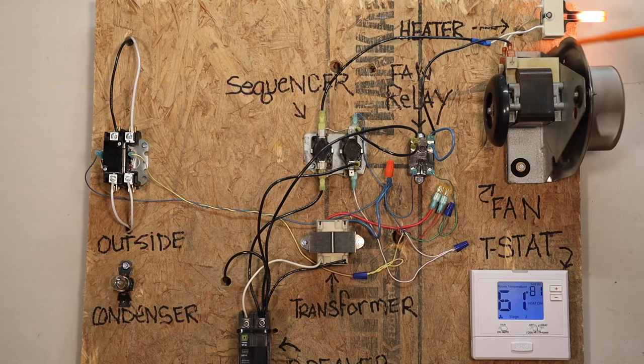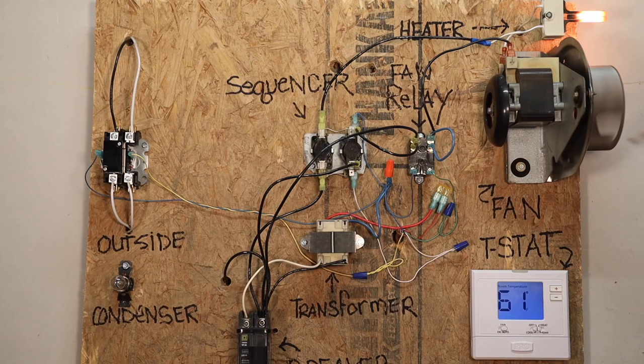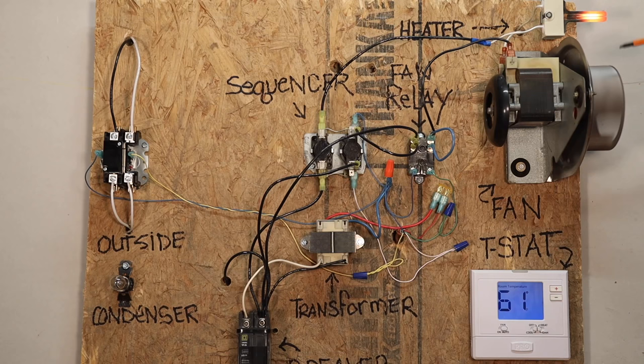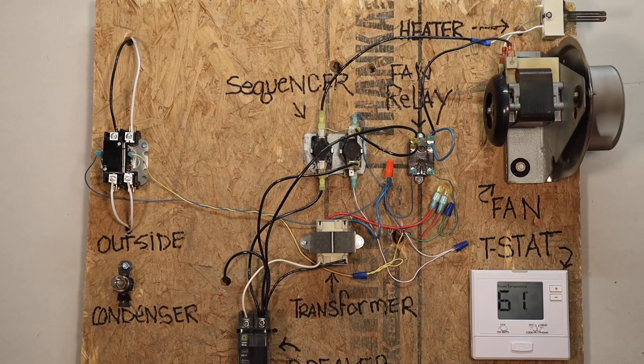And once your heater is shut off, after about another 45 seconds, your fan will shut off. And the reason why it stays running is to cool off your heating elements inside the air handler to where they are a safe temperature to be off. Then your fan will turn off.